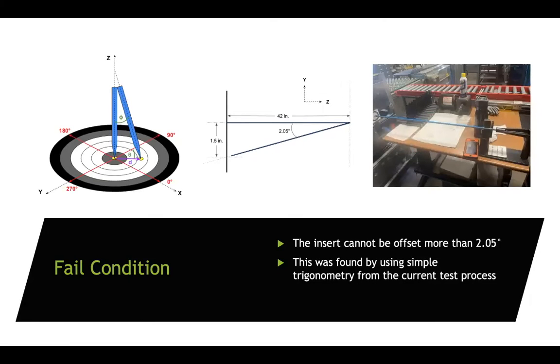As for the fail condition of this device, we calculated that by using T&T Tools' current process. Currently, they thread a 42-inch long steel shaft onto their Mighty Probe handles and measure the deflection using a 1.5-inch diameter target. If it exceeds that 1.5-inch diameter, it is considered a failed part. So using simple trigonometry, we found that 2.05 degrees was the maximum fail angle.